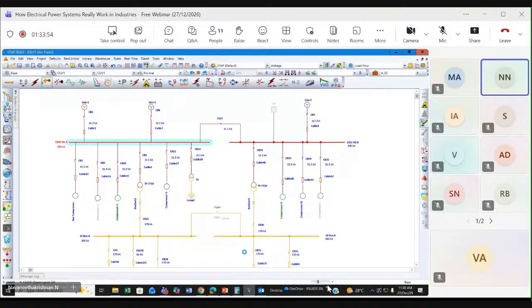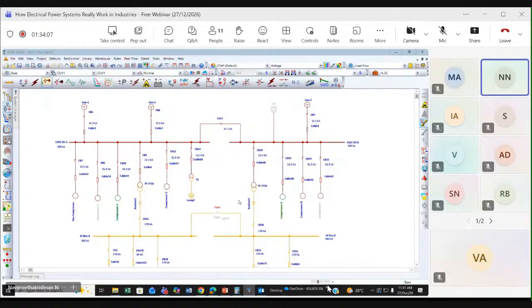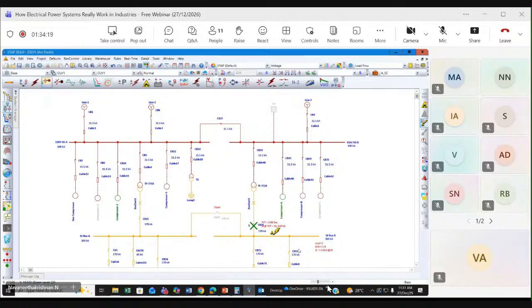Done here. I have also not modeled any relay here, because this is only a typical diagram. It will show how to coordinate relays from downstream to upstream. See here, the tripping time: arc flash incident energy is directly proportional to your tripping time. As the tripping time increases, your arc flash incident energy also increases.